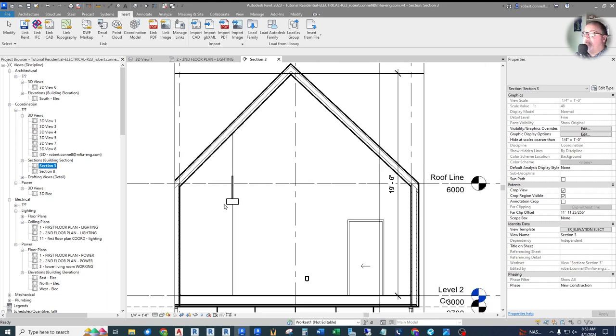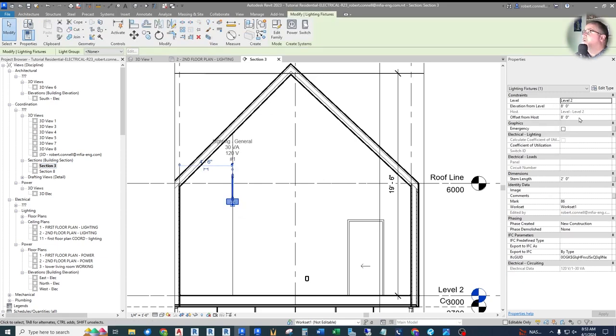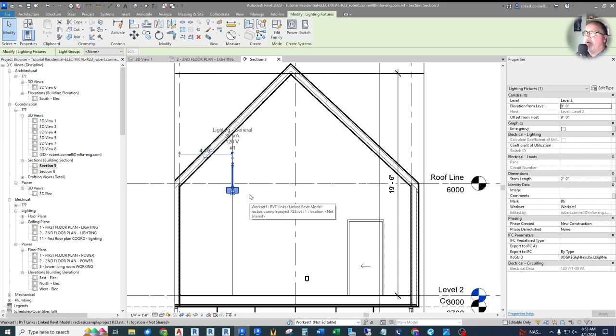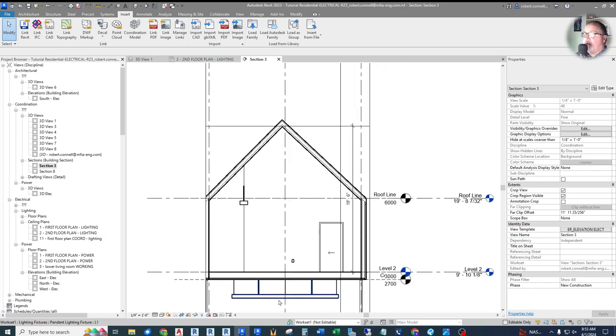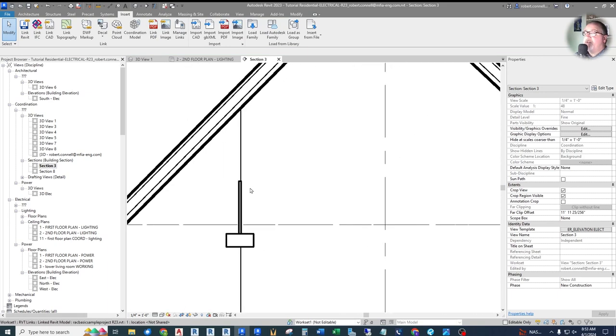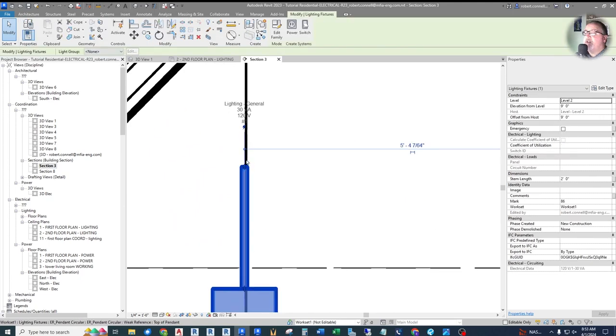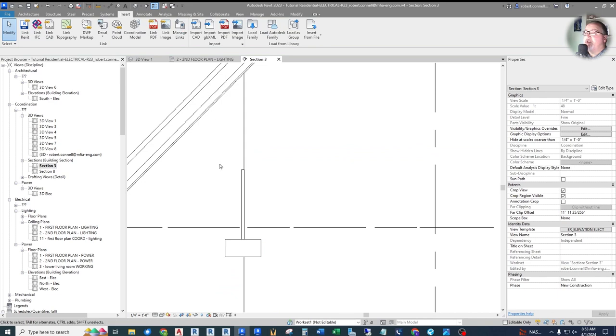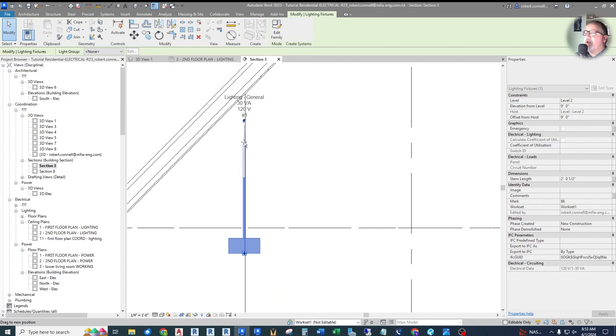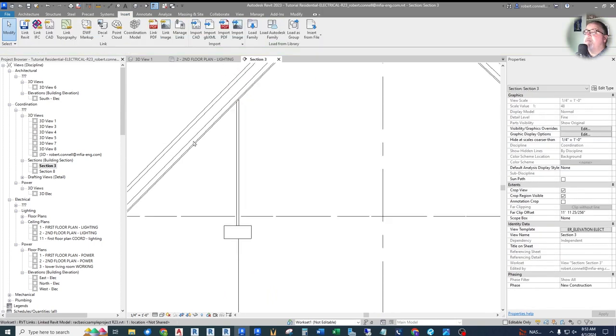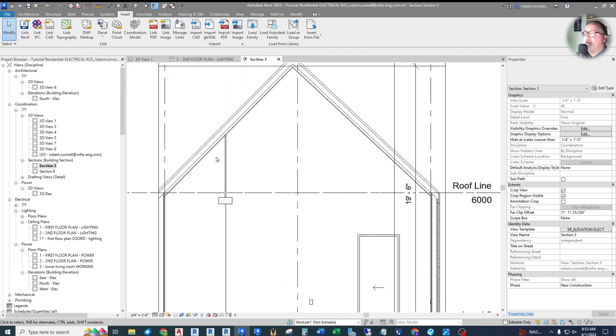The fixture is placed at eight feet. For this high vault, let's move it up to nine feet — it pops up in the section view. This custom pendant is set up so nine feet is to the bottom of the fixture. The pendant stem has an up-and-down drag arrow in section view; dragging it up stretches the stem to the ceiling, so in 3D or section it looks like a pendant hanging from the vault. The stem length is an instance parameter, so each placed light can have a different stem length.